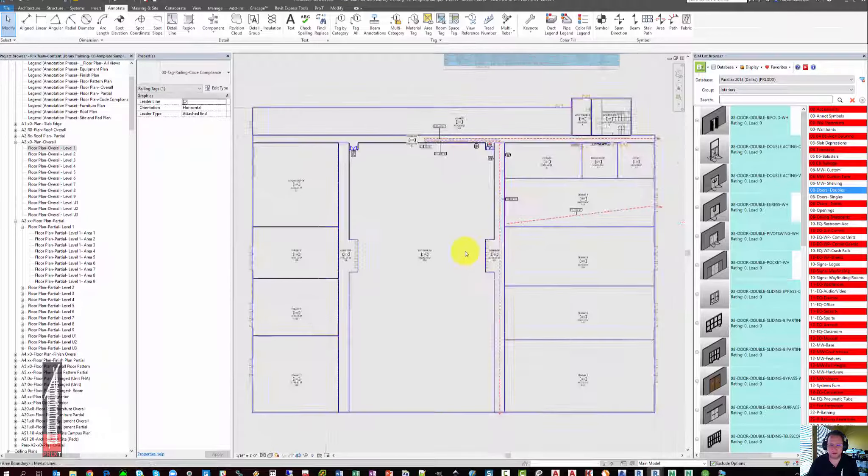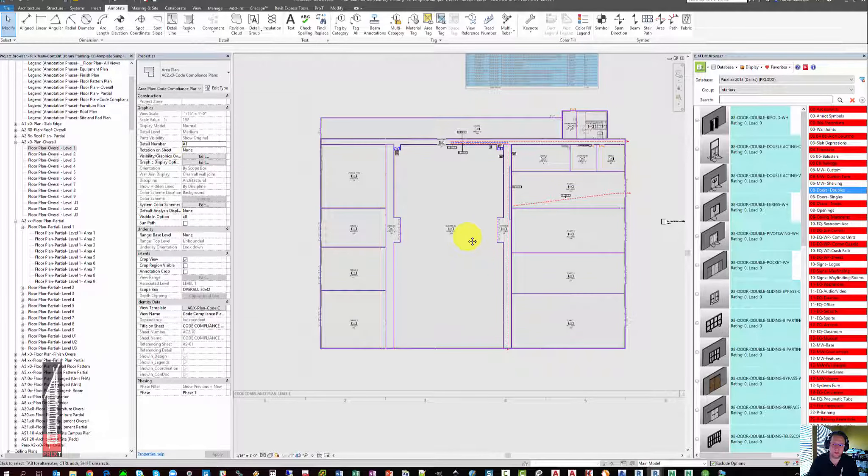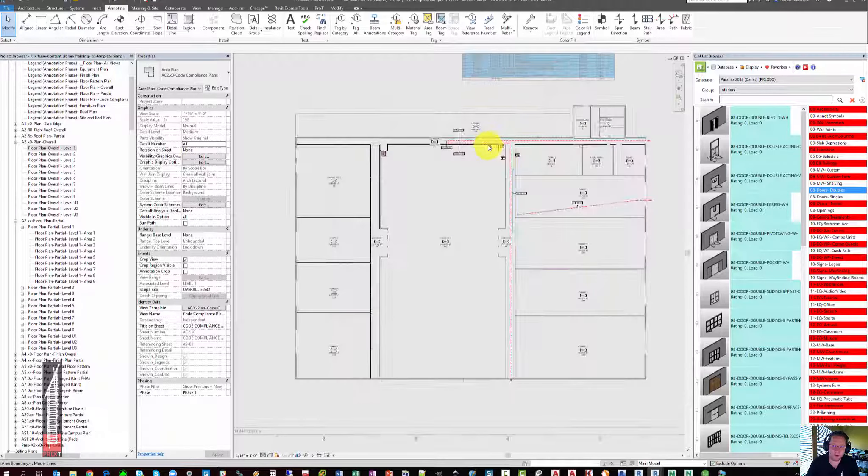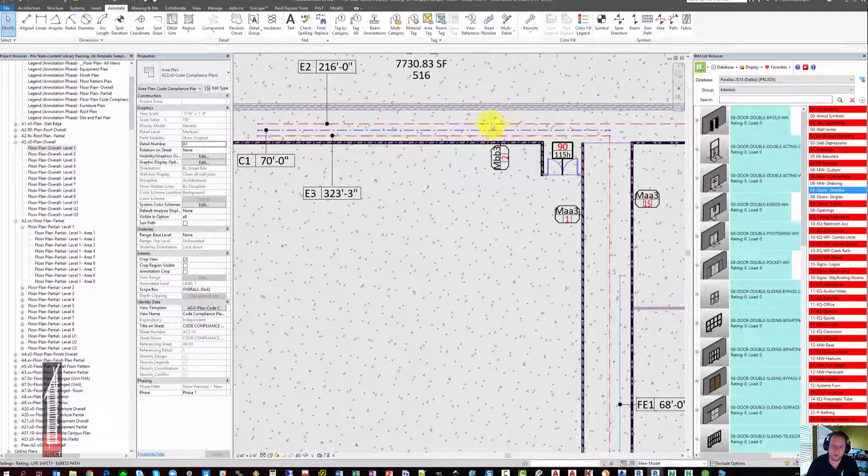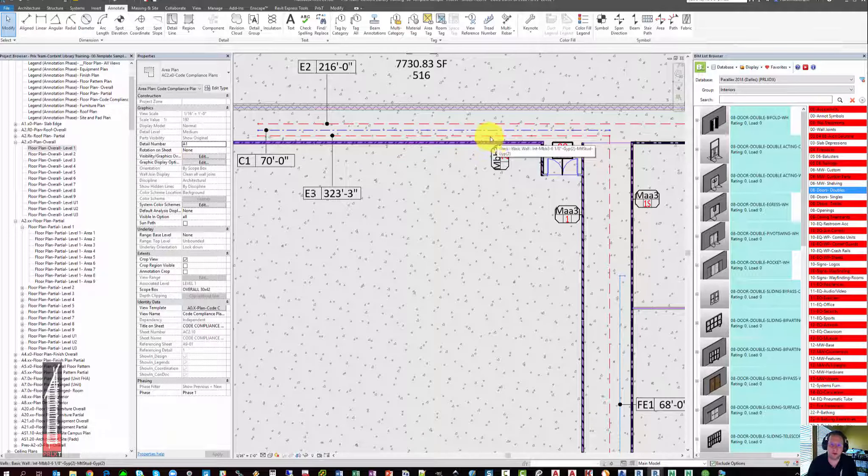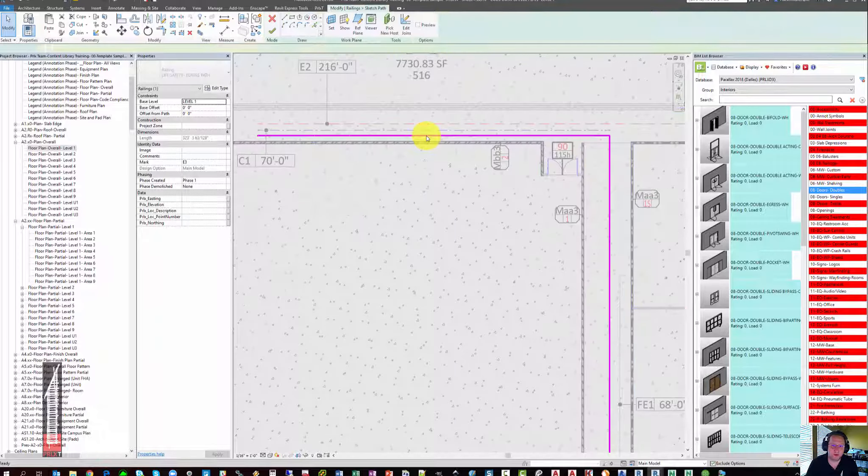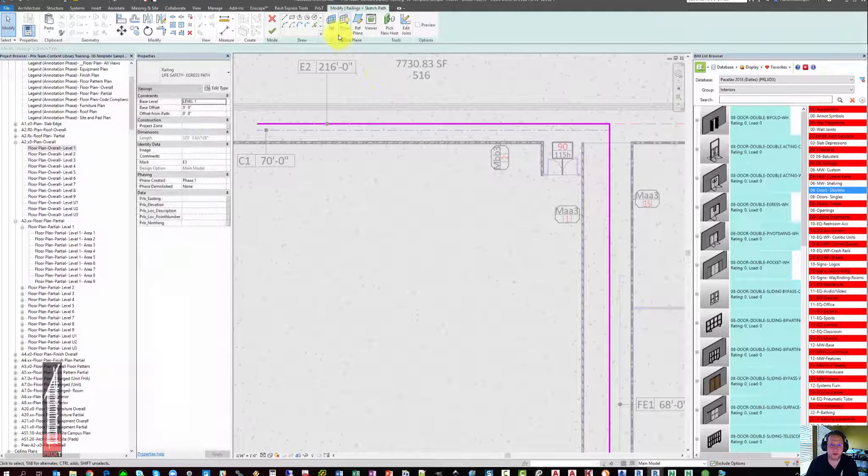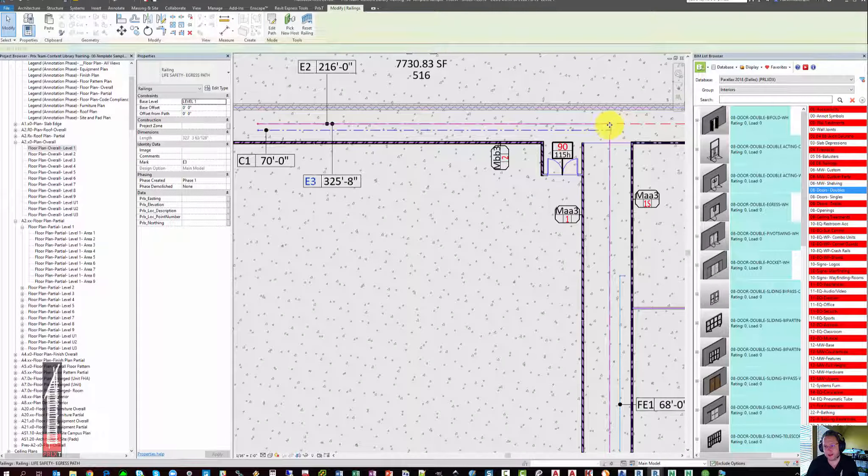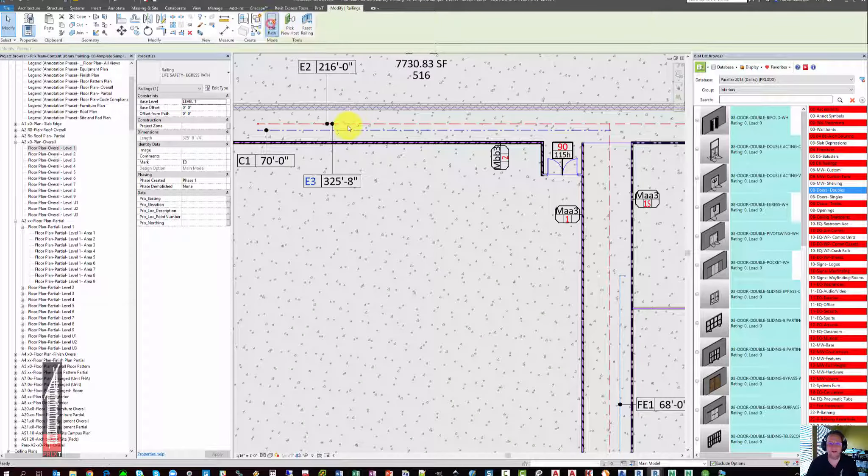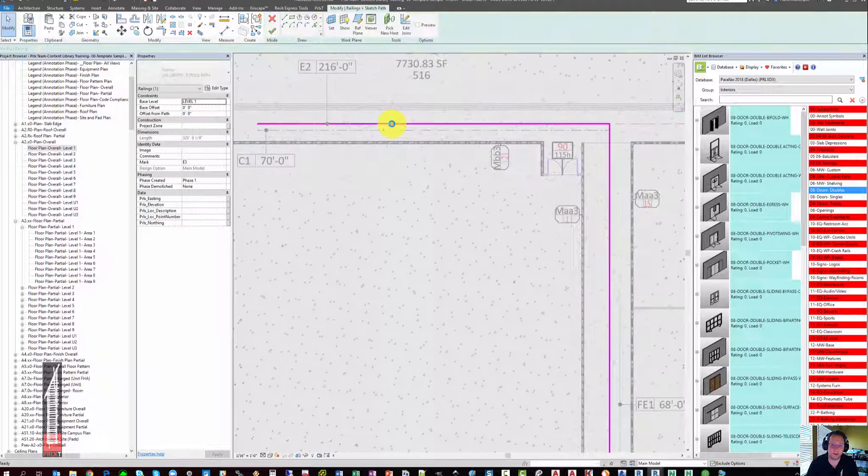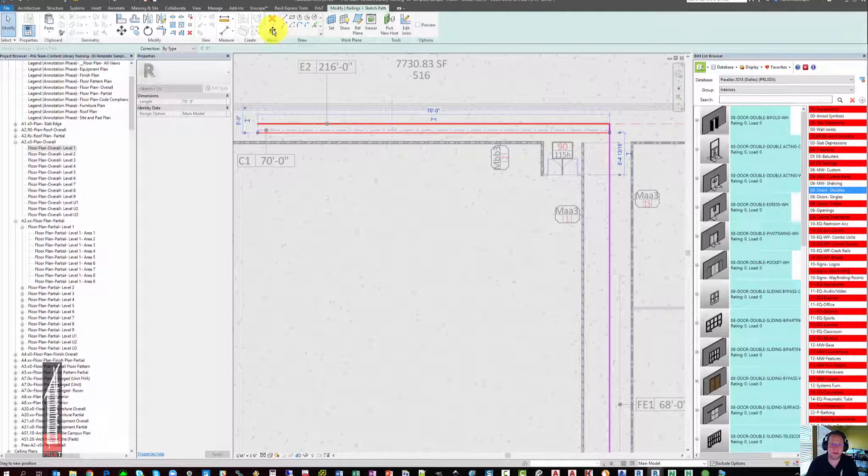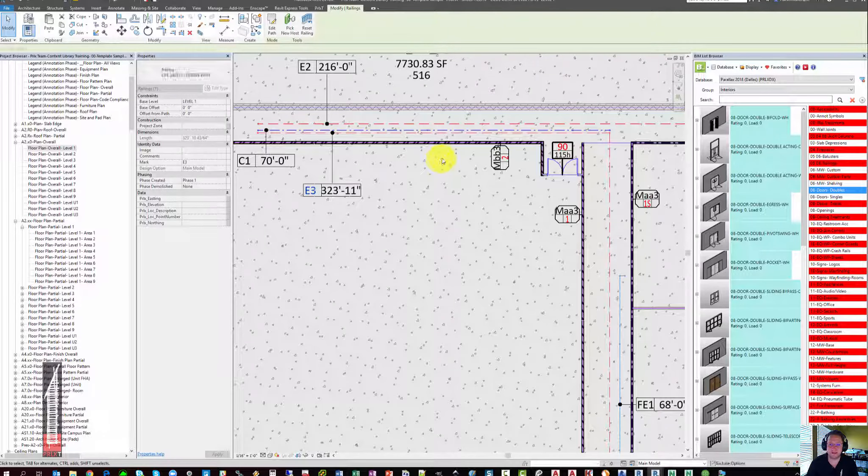This is basically the method that we use for tagging travel distances throughout our code compliance plans. Keep in mind that any areas where travel paths run next to or down the same portion of the hallway with each other, they both must be drawn in their entirety, even if you're going to overlap them for graphical simplicity. If you go to do this, make sure that you still draw this entire sketch line down to the end, as if you end the line at the intersection, you will not have the correct length. I recommend keeping them separate and just having them run parallel down the hallways where possible.